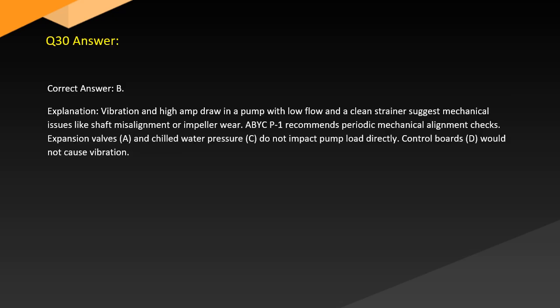Answer. Correct answer: B. Explanation. Vibration and high amp draw in a pump with low flow and a clean strainer suggest mechanical issues like shaft misalignment or impeller wear. ABYC P-1 recommends periodic mechanical alignment checks. Expansion valves (A) and chilled water pressure (C) do not impact pump load directly. Control boards (D) would not cause vibration.